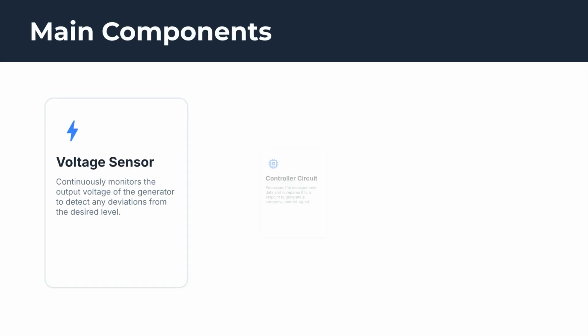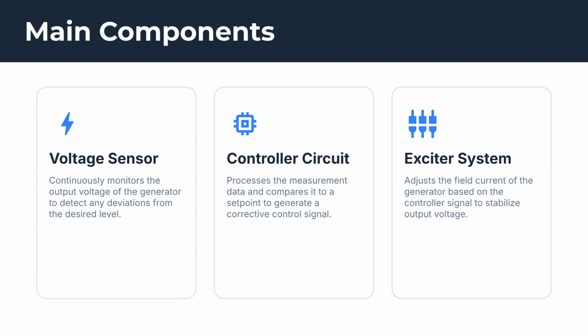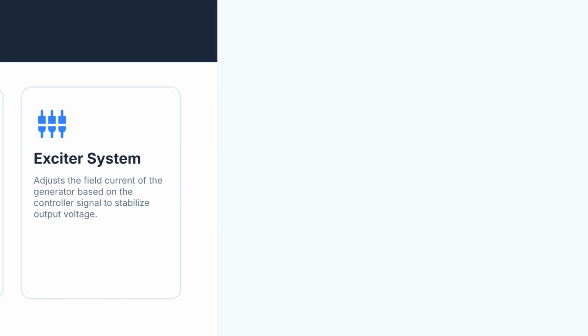The main components of an AVR include the voltage sensor, which continuously monitors output voltage. The controller circuit processes this data and generates a corrective control signal. Finally, the exciter system adjusts the generator's field current to stabilize the output voltage based on the signal.